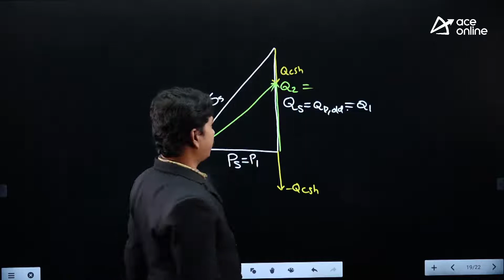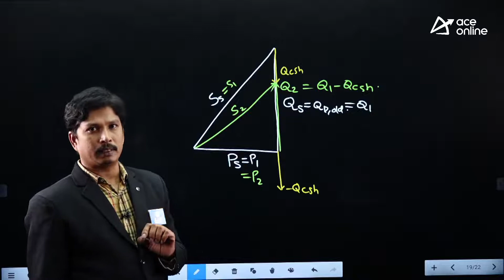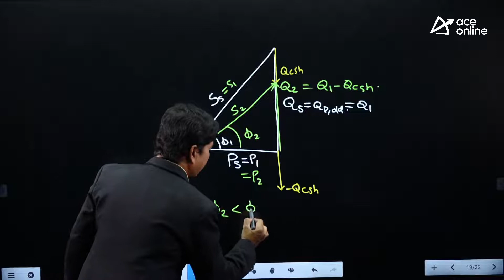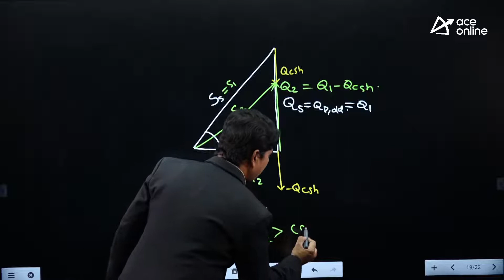And is there any change in the active power? As we are connecting a pure capacitor, the capacitor never absorbs or delivers active power, so there is no change in the active power. P1 is exactly equivalent to P2 in both cases. Clear? Now if you compare the power factor, initially this is the power factor angle phi 1, and whenever the capacitor is connected, this is the power factor angle phi 2. If you see, phi 2 is less than phi 1, therefore cos phi 2 is greater than cos phi 1.